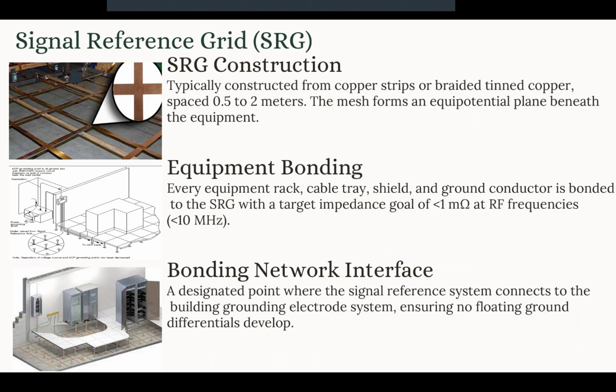We mentioned several times that one of the key components in the grounding system is the signal reference grid, the SRG. That SRG is a mesh of interconnected conductors that forms an equipotential reference plane for the electronic equipment. It is important because it provides a stable, low impedance signal reference, and it shows uniform voltage potential, so we don't have ground loops and common mode noise, and is essential basically for higher speed digital systems.